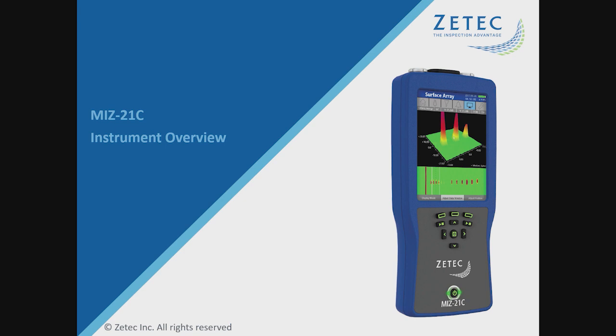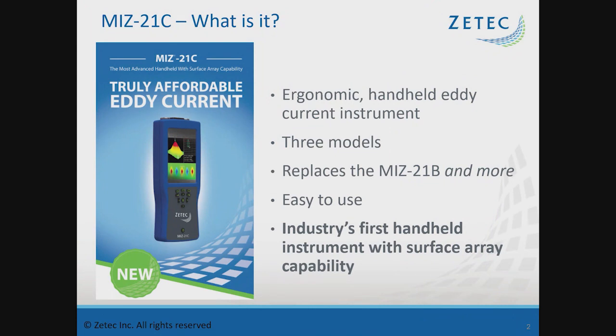I'm Jesse Heron, the eddy current systems product manager for Zetec, and I'm going to be going over the MIZ-21C instrument overview. The MIZ-21C is one of the primary instruments for the Surfex array probes. It is an ergonomic handheld eddy current instrument that comes in three different variations: a single frequency version, a dual frequency, and an array version. It's that third array version that you would be using the Surfex array probes with.